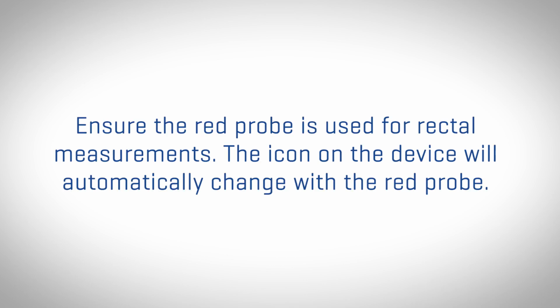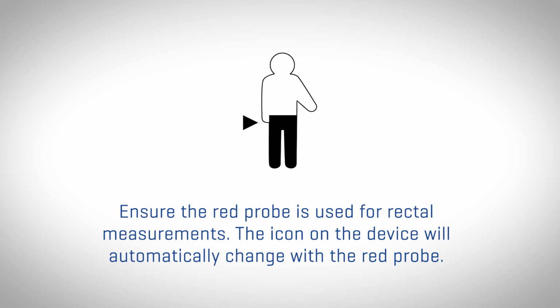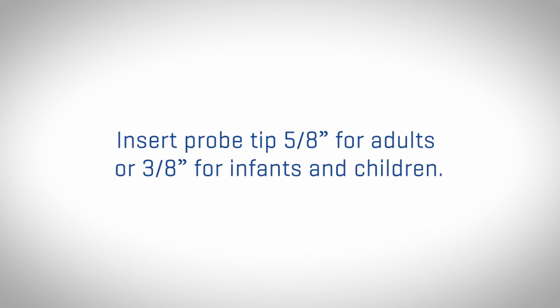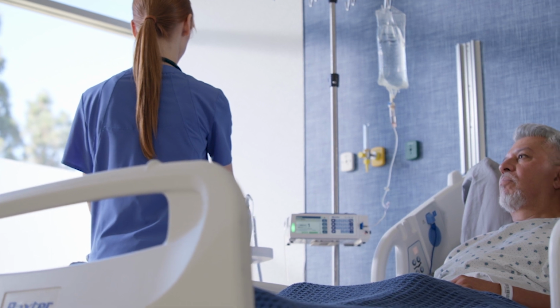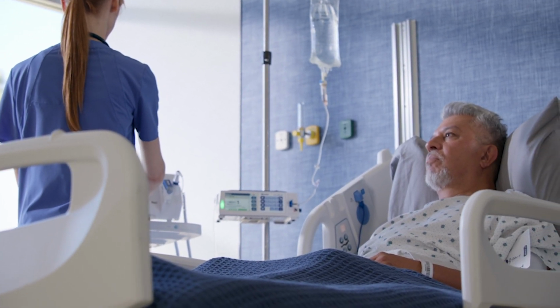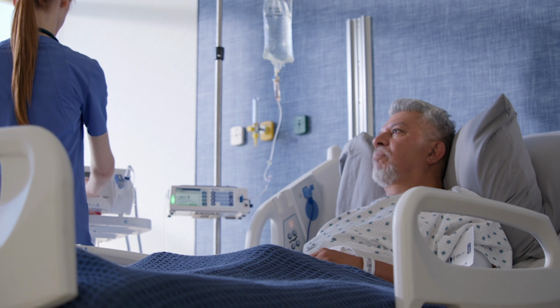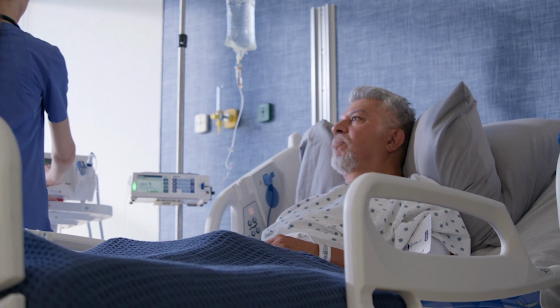Now we'll cover taking a rectal temperature in predictive mode. First, ensure the red probe and probe well are inserted into the device. Remove the probe from the well and attach a probe cover. The icon displayed on the device will automatically default to the rectal mode when the red probe is used. Next, use lubricant as needed and insert the probe tip 5/8 inch for adults or 3/8 inch for infants and children to avoid the risk of bowel perforation. At the end of the measurement, there will again be 3 short tones and the temperature will be displayed on the screen. You can release the probe cover and return the probe to the well.